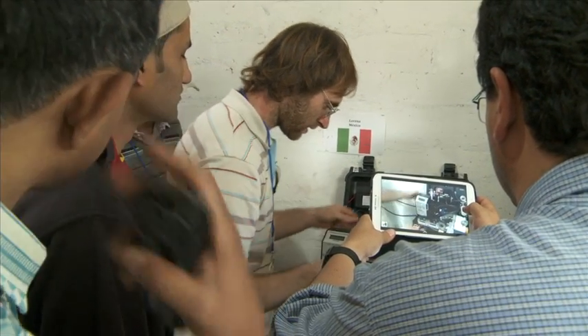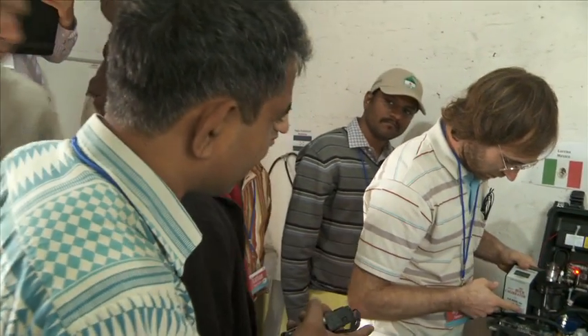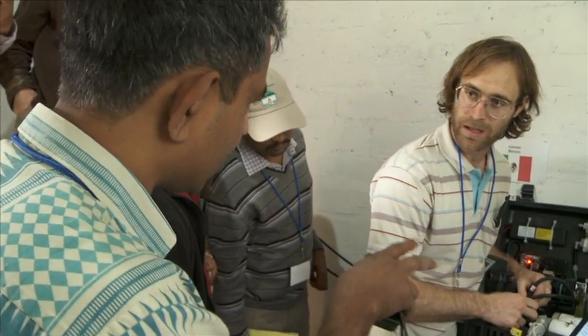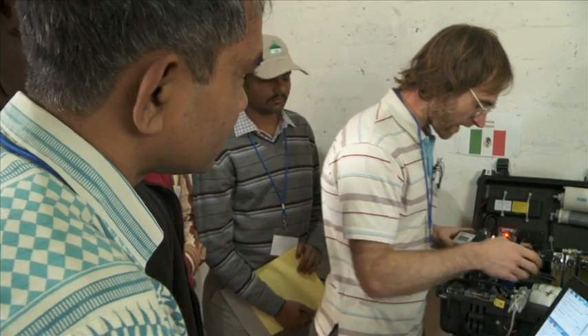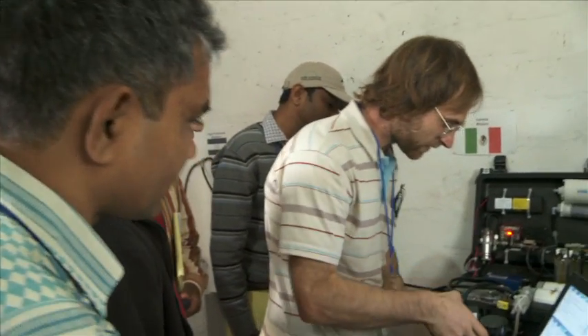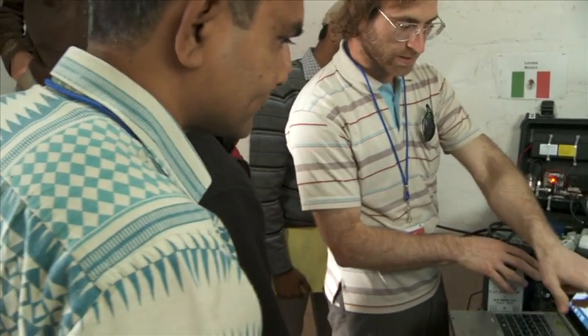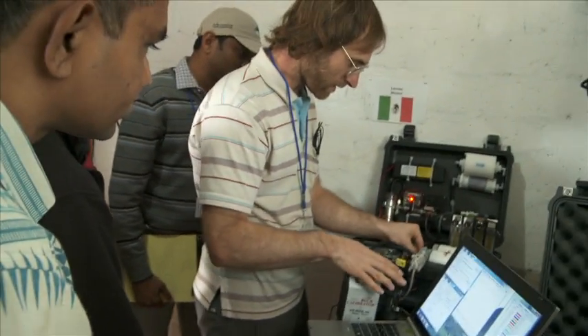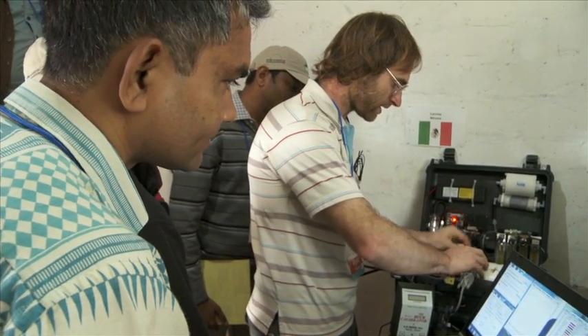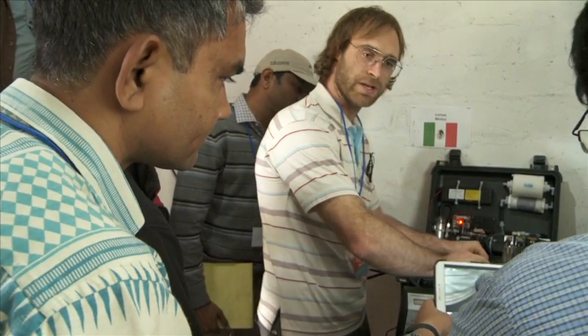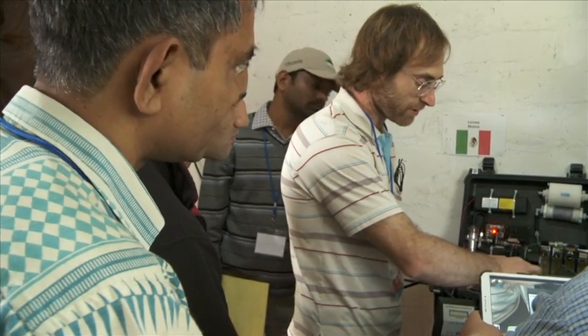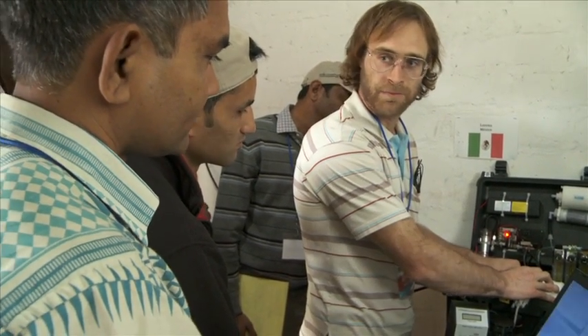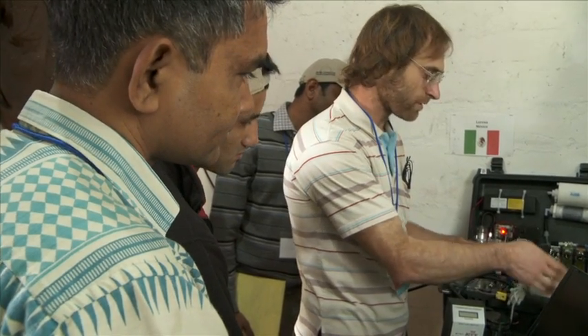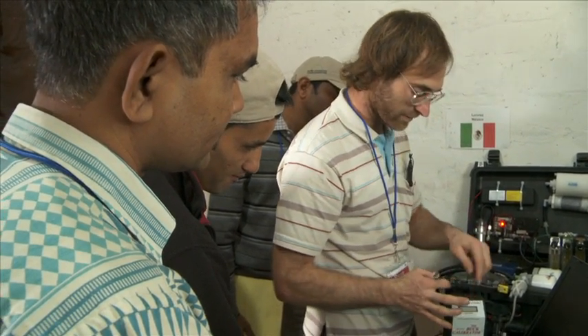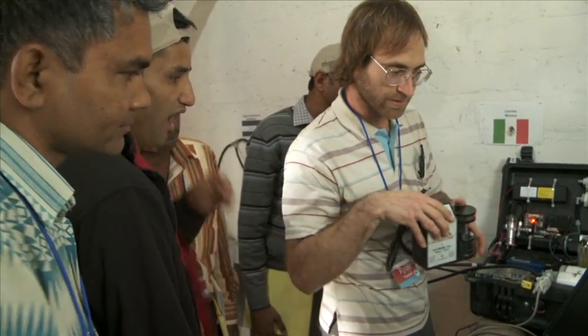So you were calibrating this for airflow? Well, no, I'm not calibrating it. I'm setting the flows. We have digital flow meters that are also logging the data and showing the flow here. But they're hard to keep calibrated because when we do sampling, we're always changing elevation. Every time you change the elevation, it changes the pressure and it changes the volumetric flow rate. So we usually just use those to watch the flow to make sure it's stable, and then we set the flow with this. That's the procedure we've been using, and it seems to work pretty good.